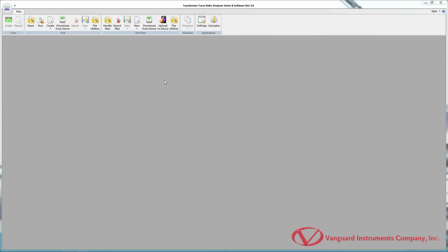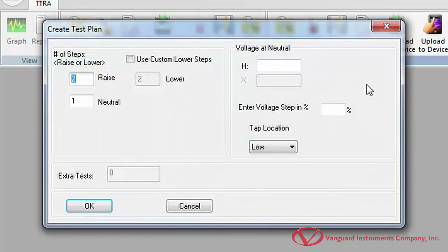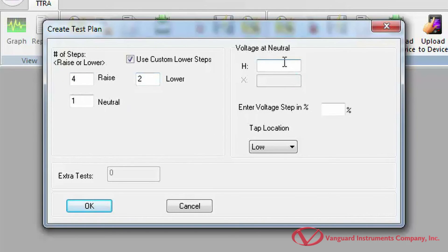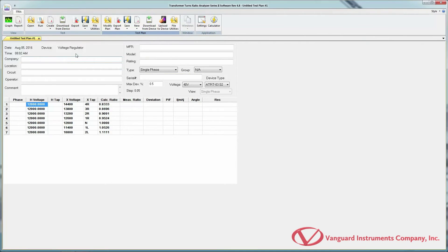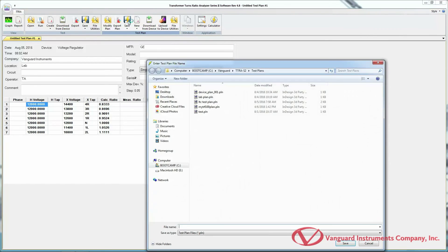Now let's create a test plan for a voltage regulator. Click the arrow below the New icon in the Test Plan command group and select Voltage Regulator. Enter the number of raise steps and neutrals. If the number of lower steps is not the same as the raise steps, check the Use Custom Lower Steps checkbox and enter the lower steps. Enter the H voltage value at neutral and the voltage step in percent. Select the tap location and click OK. Now you can enter relevant header information, select the test voltage and Vanguard Transformer Turns Ratio Tester model, and then save your test plan.